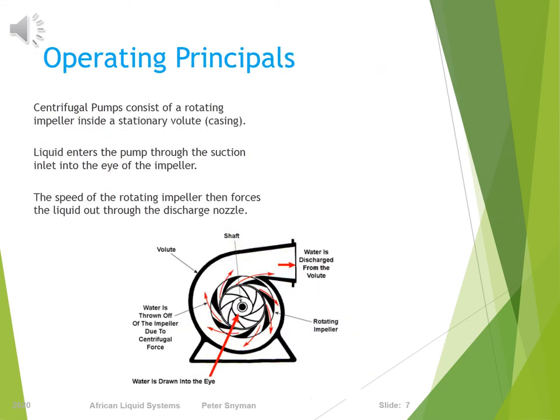The operating principles of a centrifugal pump: this group of pumps consists of a shaft-mounted impeller or impellers rotating unidirectionally within a casing. The liquid enters the eye of the impeller and acquires energy in the form of velocity as it passes through the impeller passages. The velocity head is converted into pressure head by the volute or spiral-shaped outer casing of the pump, which directs the liquid from the outer perimeter of the impeller to the pump discharge.